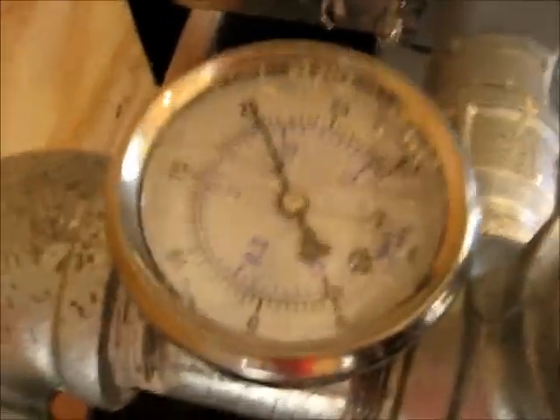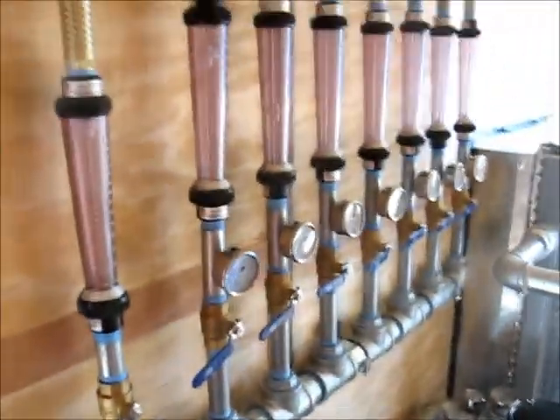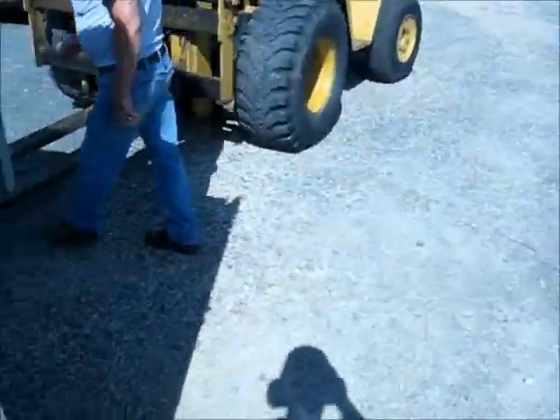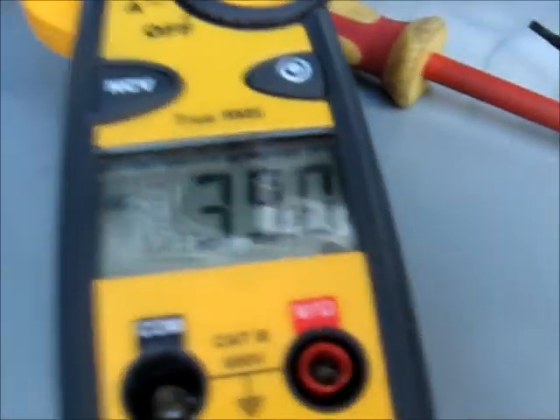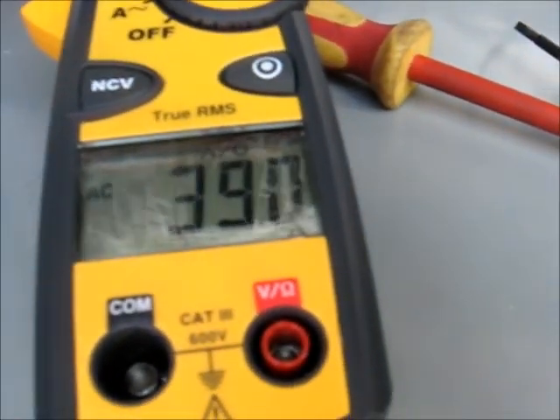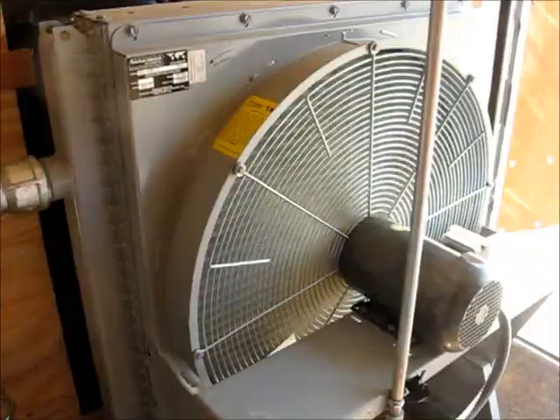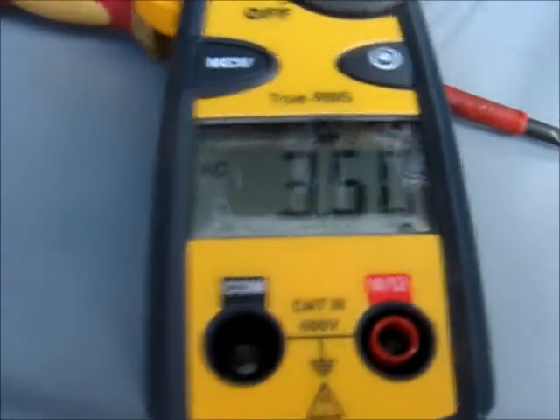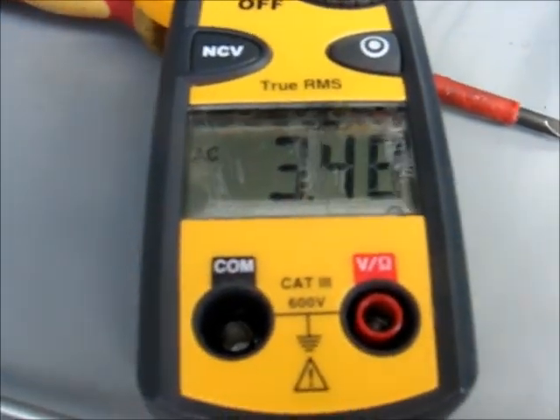Yes, the air compressor is running. We're about 20 psi. We're going to take an amp reading. About 38, 39 amps out of a possible 47. Heat exchanger is running. We want to go check the amps. Out of about 3.5 amps, which is good.